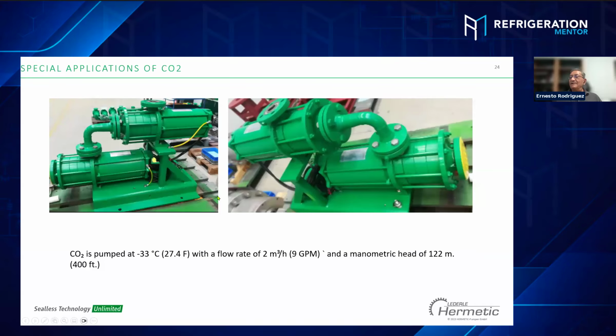We have a very special application lately for CO2, where we need a very low flow rate and a high differential pressure. This is an example of using two pumps in series to meet this low flow, 9 gallons per minute and 400 feet. This is very special. I see it most in data centers and in some petrochemical applications. Some of my technician friends have experience with this application, but it's very special.